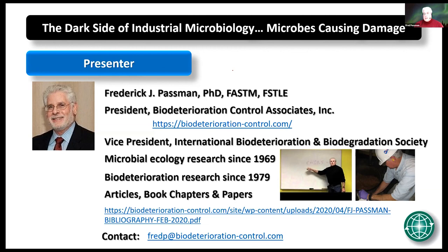As fuel becomes more severely refined, and as we go to biofuels, they tend to be more readily biodegraded and more susceptible. They hold more water, and therefore more easily provide a suitable environment for microbes to grow in the tanks and cause fuel tank deterioration.